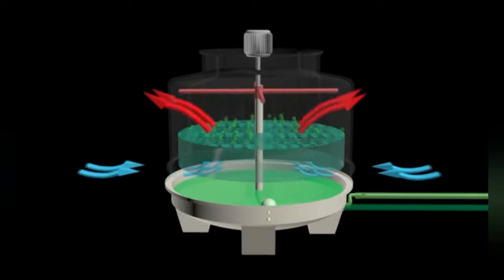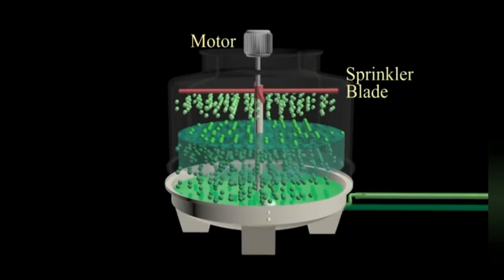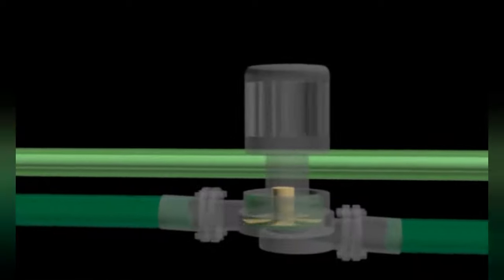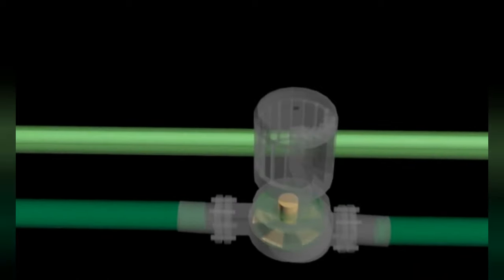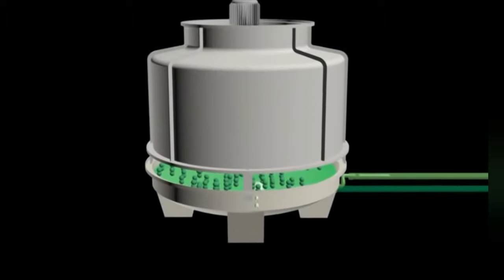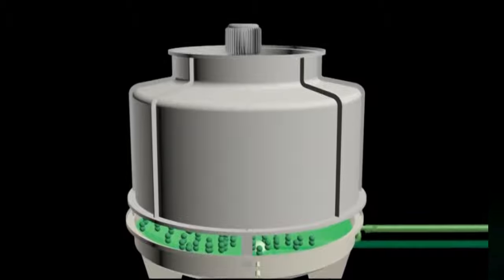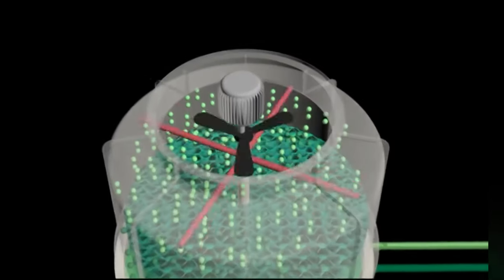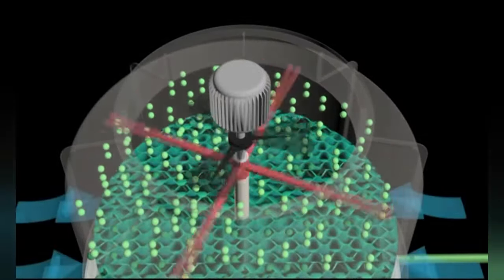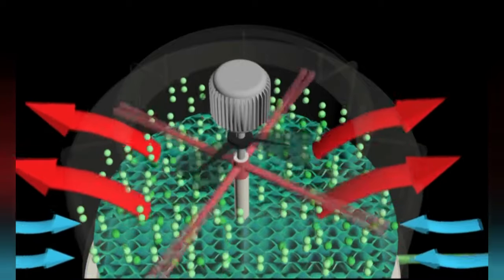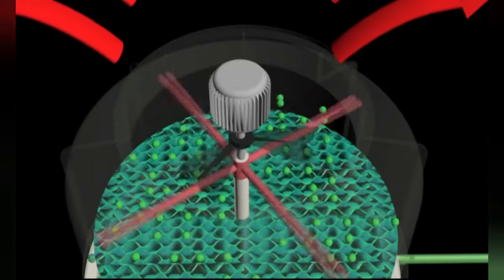The cooling tower consists of several components: motor, sprinkler blades, water fins, water reservoir, buoys, and a make-up water tank. Condenser water flows to the cooling tower with the help of centrifugal pumps, referred to as condenser water return. This water passes through rotating sprinkler blades driven by the water pressure itself. Water then cascades down through the fins, which slow the descent so that heat can be absorbed more effectively by the surrounding air passing through the fins.